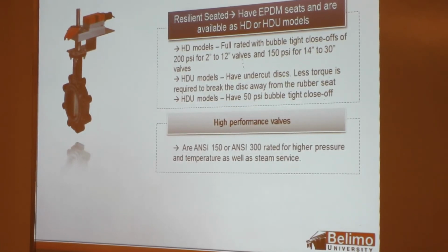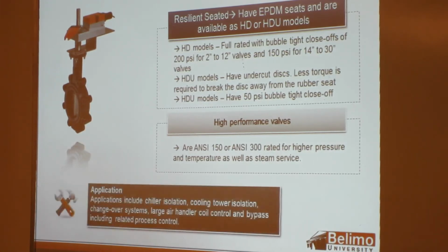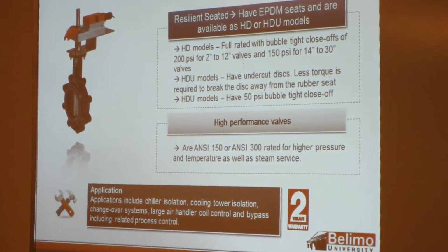Then we also have high-performance butterfly valves that are metal-to-metal seating. We don't have EPDM rubber seats. They're available in ANSI 150 or ANSI 300 rated configurations, and they are good for steam as well. Applications: chiller isolation, cooling tower, changeover, large air handlers, bypass. I'd say probably the two I see the most are chiller and cooling tower isolation valves. And this is, I think, the third of the valves that we have that are 2-year. The rest are going to be 5-year.